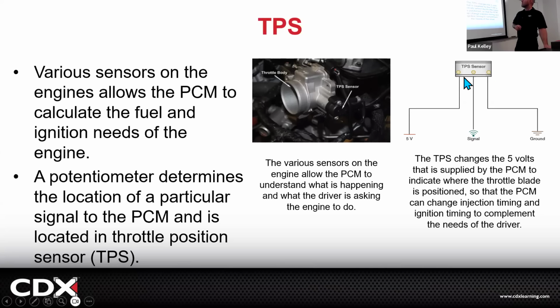With signal, we'd usually probe right here, and let's say it's 50% throttle, you're getting 2.5 volts. You should get 2.5 volts also at the ECM. If it's got 2.5 volts at the sensor but not at the ECM, it'd be an open in the wire. Or if it doesn't have 2.5 at the TPS at 50% throttle, that sounds more like an open in the sensor. We just have to verify the sensor gets the 5 volts and the ground it needs. We'll go more over how these sensors are inputs to the system.